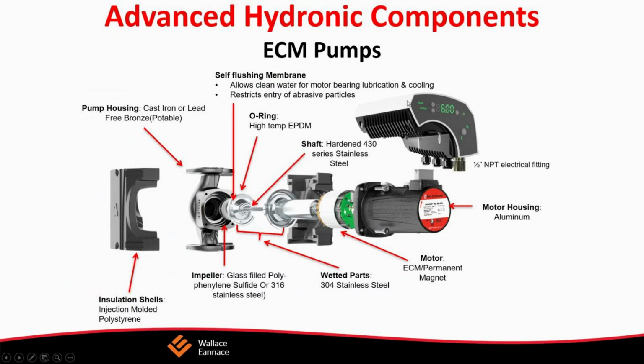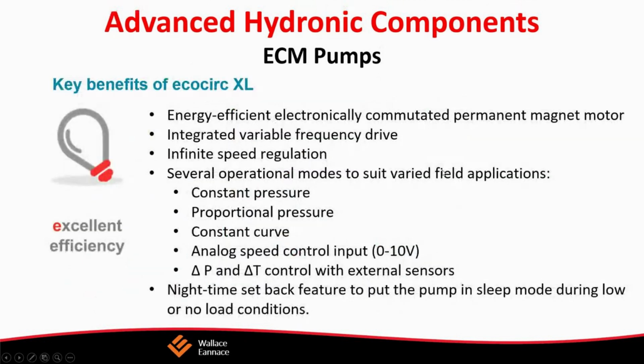It comes in cast iron. Actually, that's a mistake there. It's no longer bronze body. They are stainless steel pumps, and they're used for heating, cooling, and potable water applications. In potable water applications, we have stainless steel pumps where you no longer need an aquastat. You can set that pump to modulate based on the temperature of the water. It has a built-in temperature sensor.